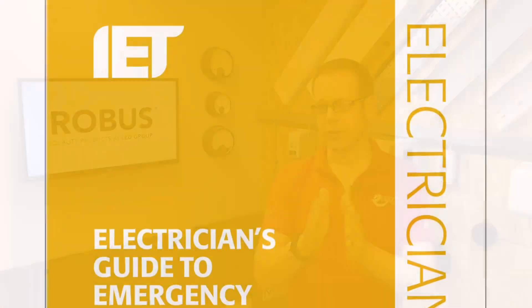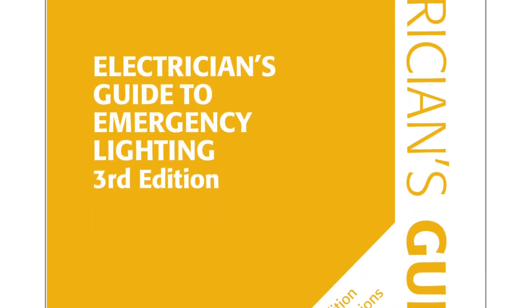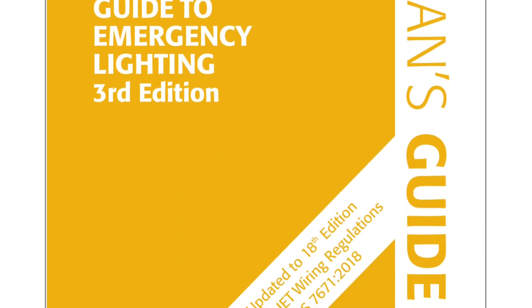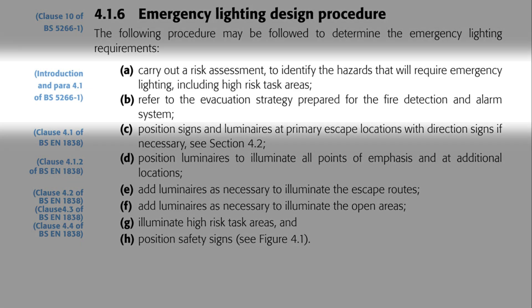Rather than diving straight into escape route illumination, the Electrician's Guide to Emergency Lighting suggests a different approach to emergency lighting design. Under subheading 4.1.6 we should follow this procedure: A — carry out a risk assessment to identify hazards that will require emergency lighting, including high risk task areas; B — refer to the evacuation strategy prepared for the fire detection and alarm system. More on risk assessments in a future video, but do make sure you understand the evacuation strategy properly.